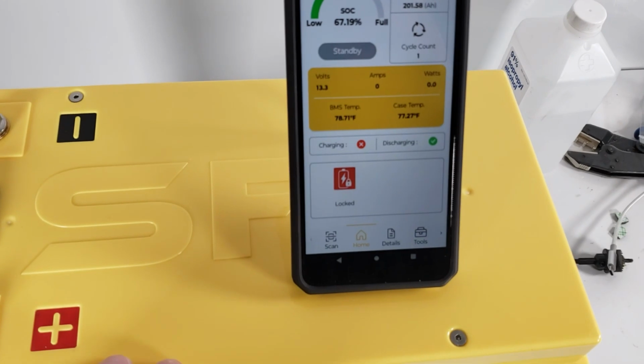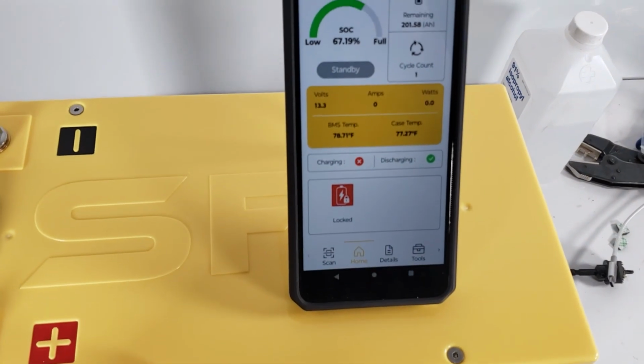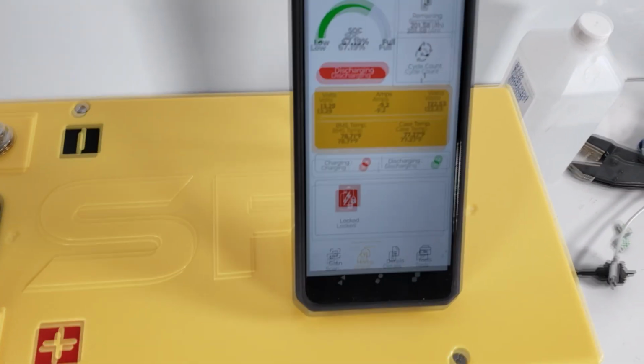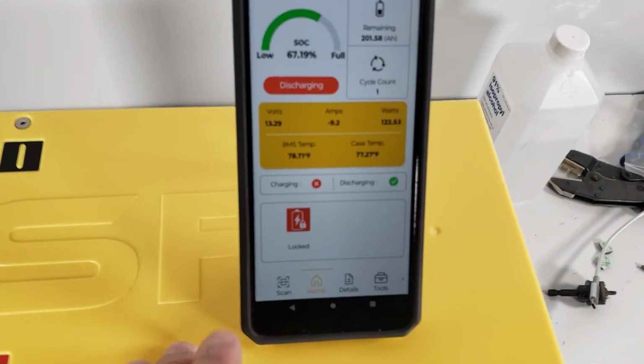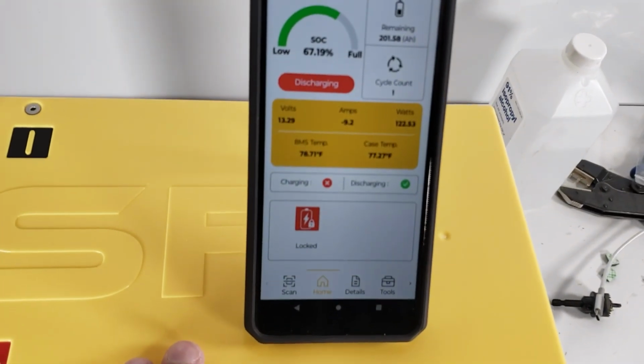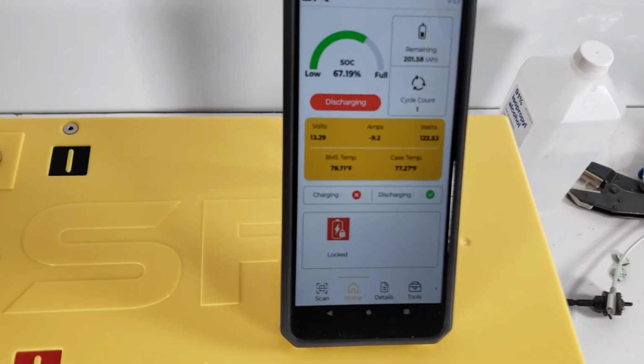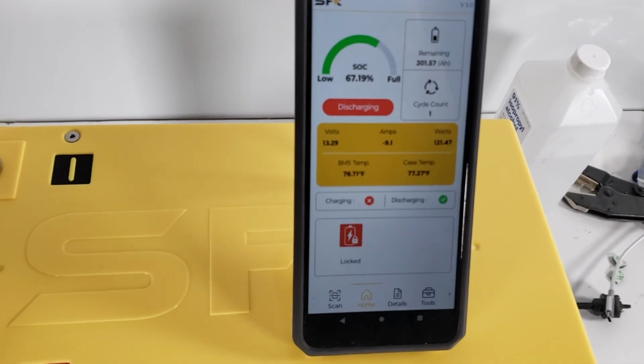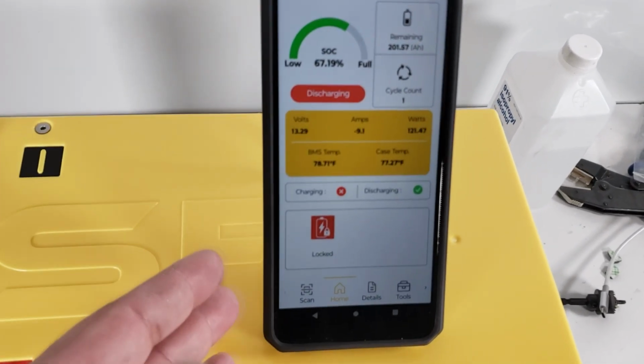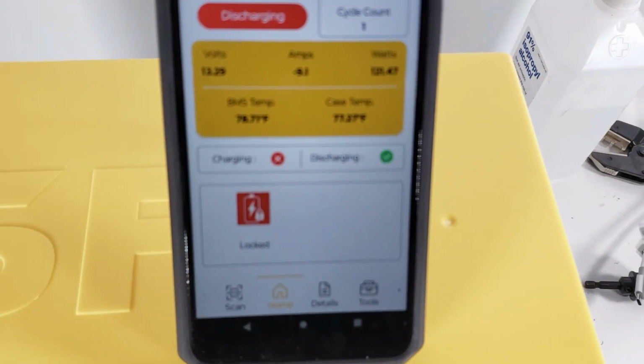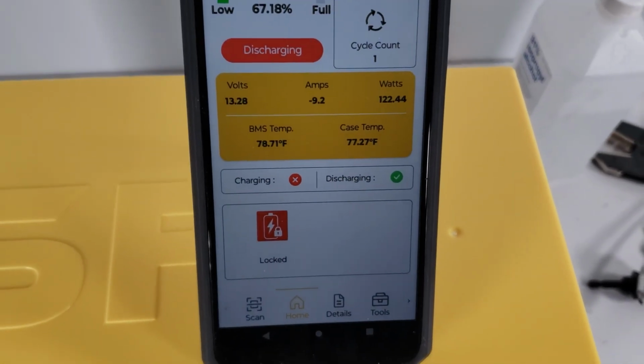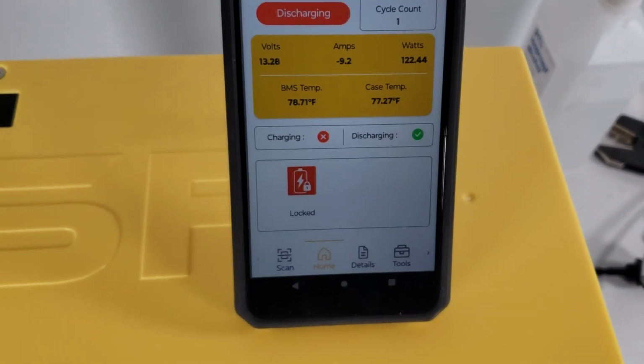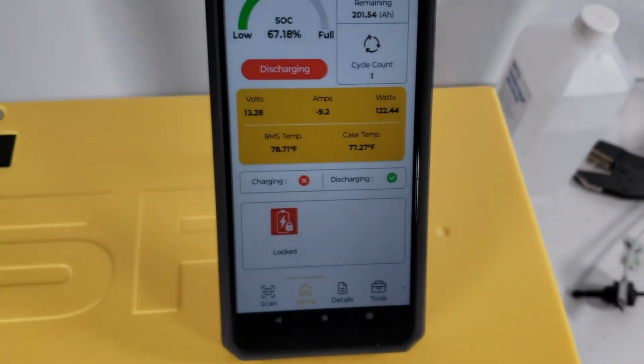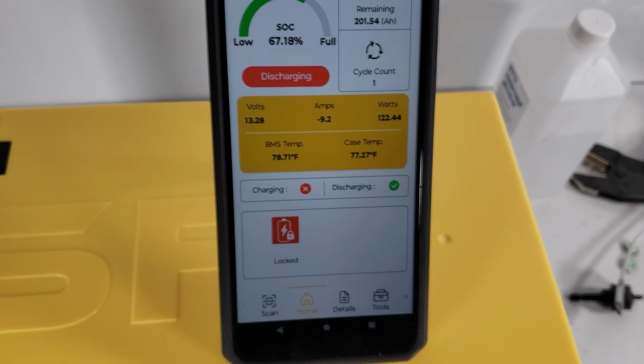Mode 2 probably isn't going to do anything either... oh, it is. We can see in mode 2 we are discharging and drawing about 9 amps. So it is actually going to draw a little bit to raise the temperature up to, I'd say, somewhere in the neighborhood of 80 or so degrees. It will run until you reach that point.